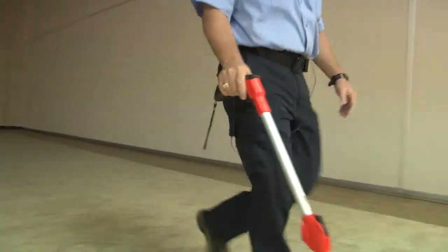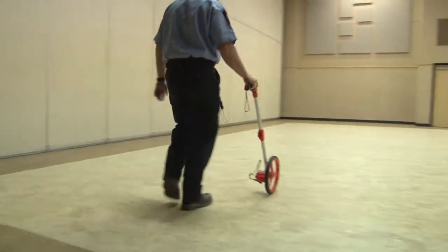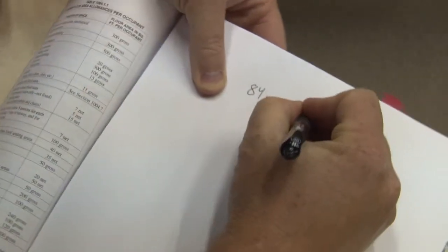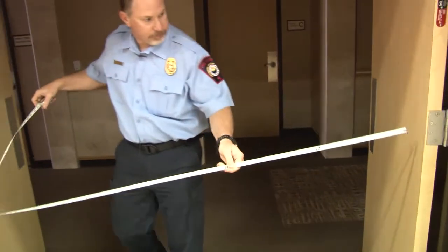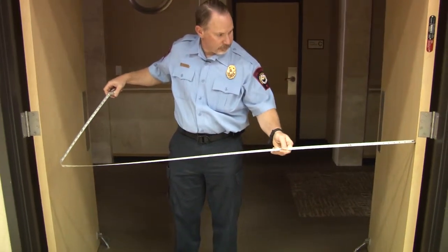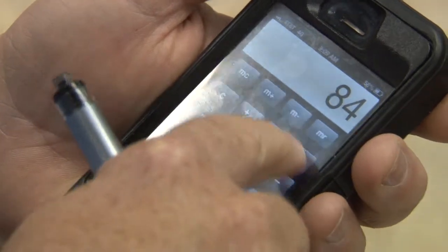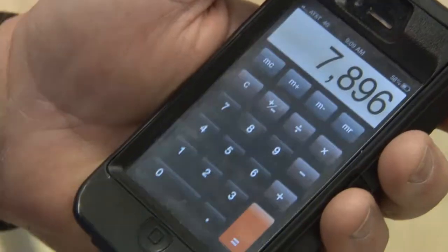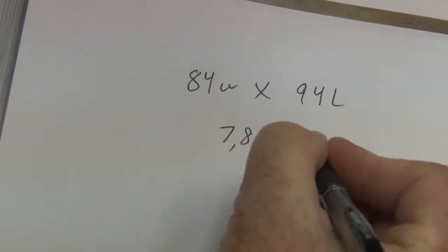So typically when we do an occupant load, if we go in and calculate that number for the floor area, we then come back and say, okay, do we have enough door capacity width? There's some math that goes into that, and we find out, for instance, that there's not enough capacity width, and we're going to lower the occupant load to accommodate the doors. So we're always going to be very conservative with our numbers.